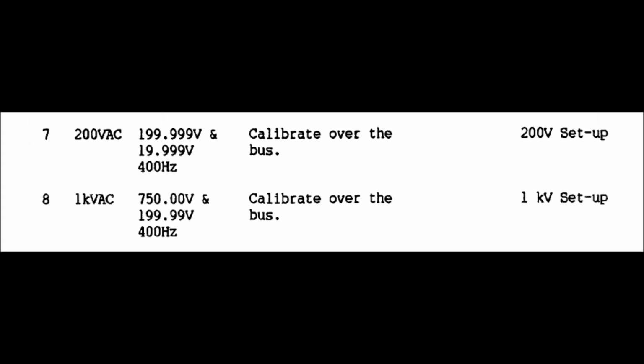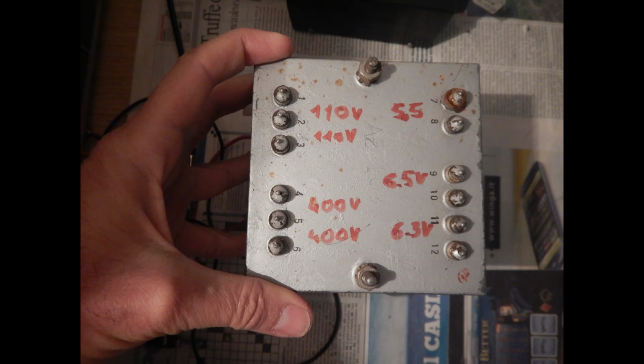But there is another problem. To calibrate the higher voltage ranges, we need a source of high voltage going to about 700 volts, and that could be obtained with a power transformer, except the manual requires these AC voltages to have a 400 Hz frequency, so that rules out mains operated transformers. That would of course provide a 50 Hz AC voltage in this part of the world. However, a transformer like this still works even at 400 Hz, albeit with probably different voltage ratios. So all I need is a way to generate some low voltage 400 Hz AC signals.